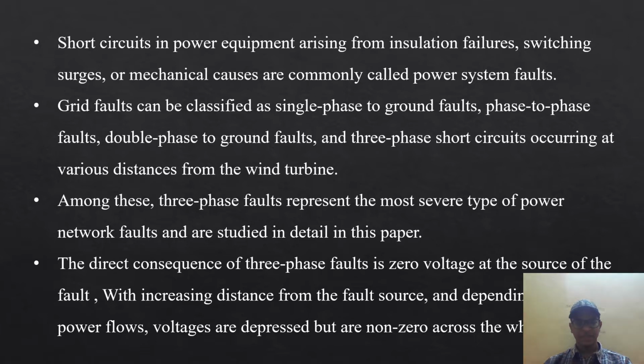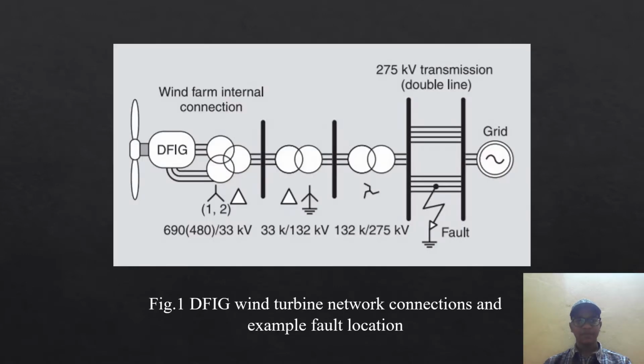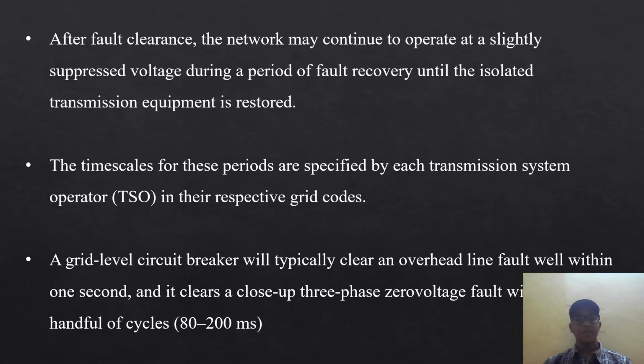A direct consequence of the three-phase fault is zero voltage at the source of the fault. Here is the diagram of DFIG wind turbine network connections and an example of fault location. After the fault clearance, the network may continue to operate at slightly suppressed voltage during the period of fault recovery until the isolated transmission equipment is restored. The timescales for these periods are specified by each transmission system operator in their respective grid codes. The grid level circuit breaker will typically clear an overhead line fault well within 1 second, and it clears a close-up three-phase zero voltage fault within a handful of cycles, 80 to 200 milliseconds.